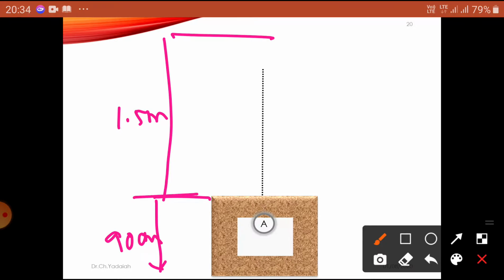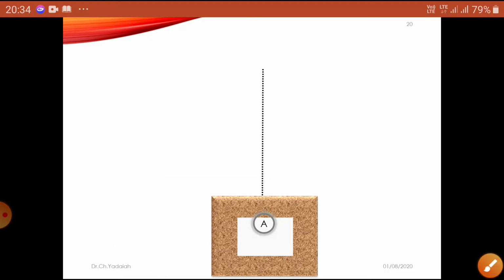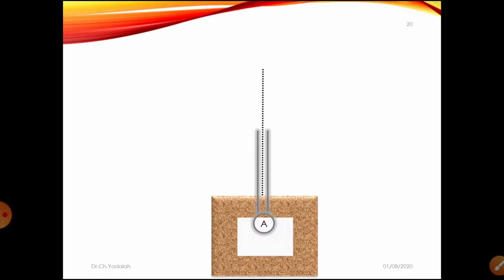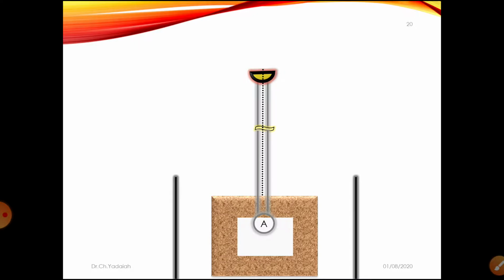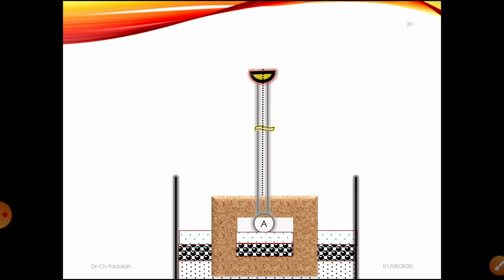That means we place our plate in the ground at a depth after 1.5 meters. After placing the copper plate, we connect the same 19 mm GI pipe as usual, connected to our funnel with wire mesh. For length purposes I use some breaking arrangement, leaving a gap to fill with charcoal and coke. Fill 15 centimeters of salt, 15 centimeters of coal, alternating salt and coal layers up to nearly 1 meter, covering the 90 centimeter copper plate.